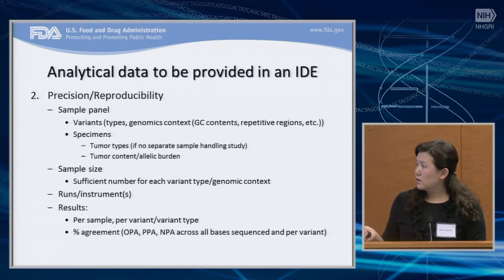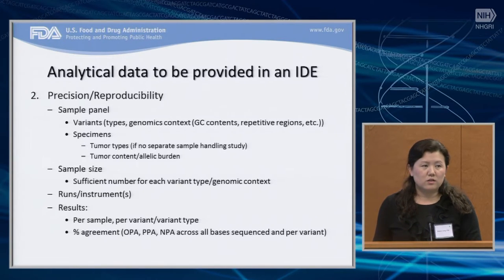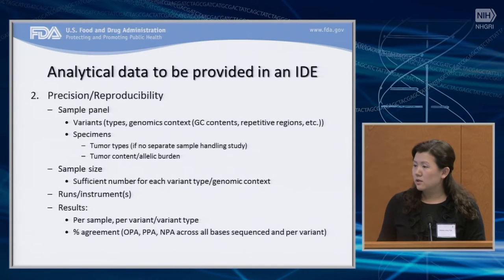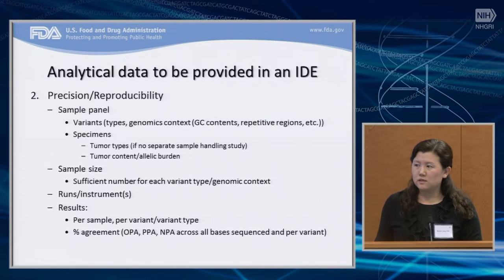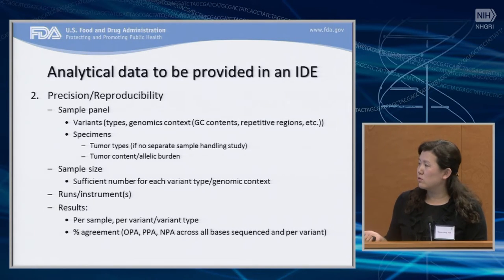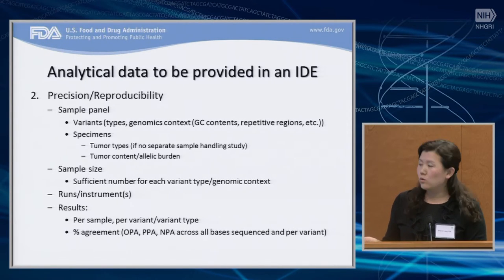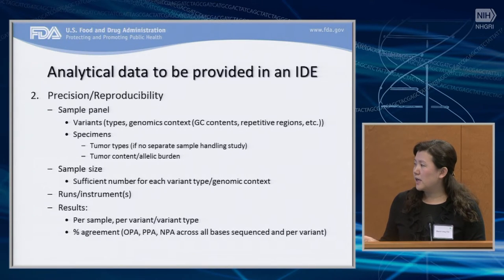Of course, tumor contents and tumor types seem oncology-oriented, but this can be generalized to other applications. If you have questions, you can talk to us through the pre-submission process and we can give comments or suggestions to your questions and proposals. For the precision and reproducibility studies, you want to include different runs or different instruments if applicable, using the same methods to summarize the results.